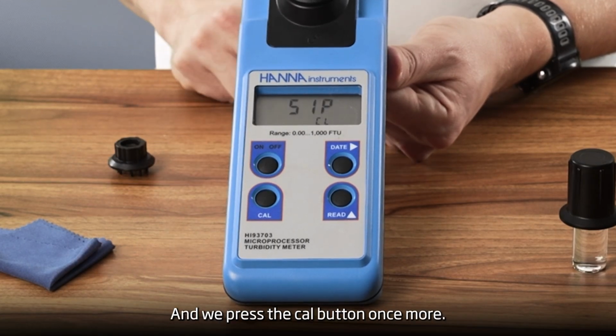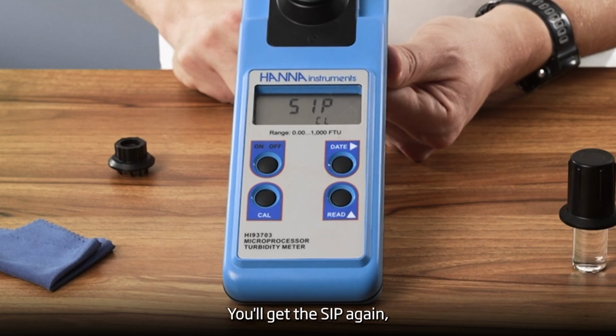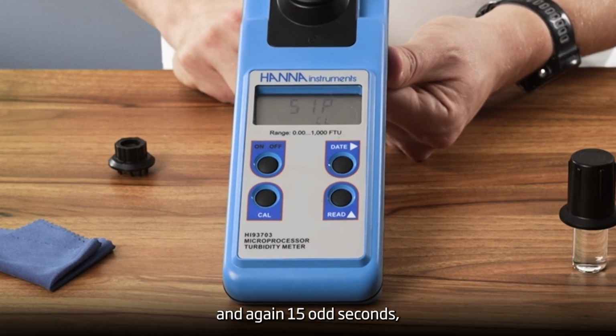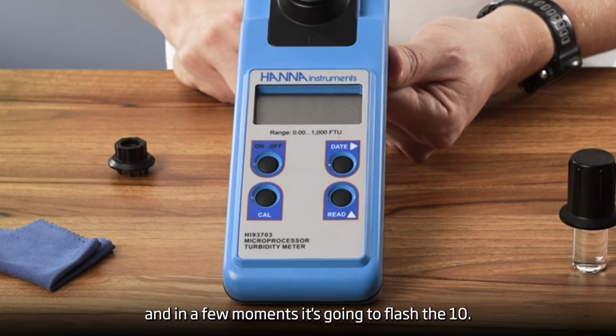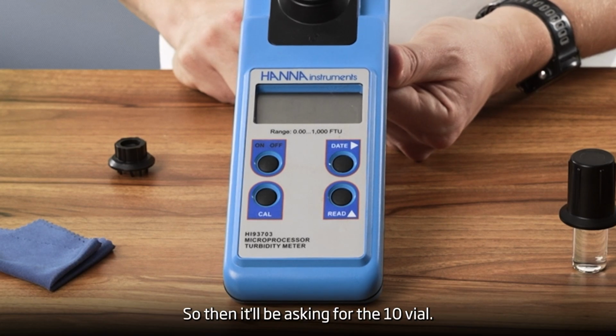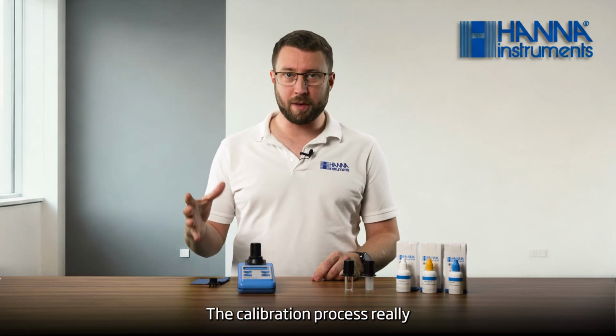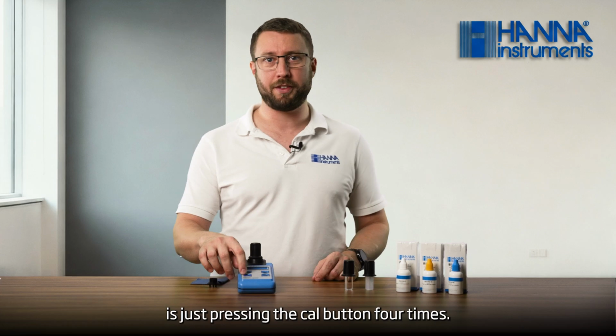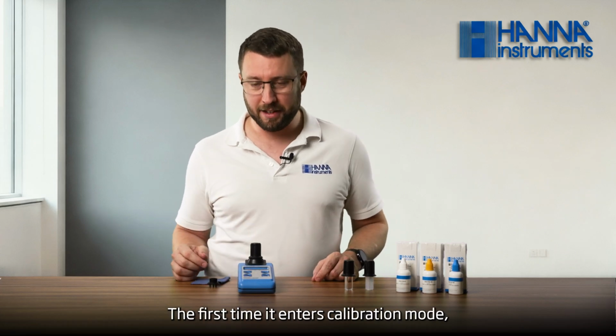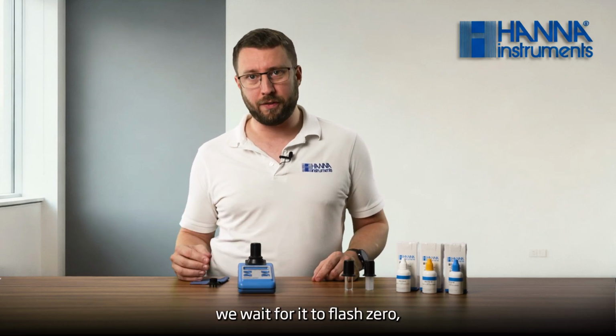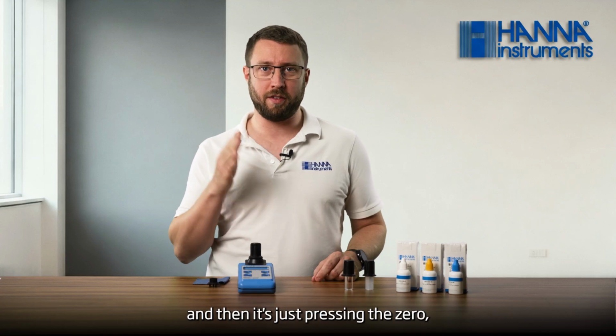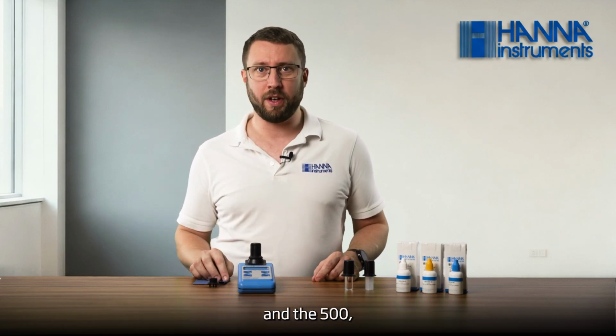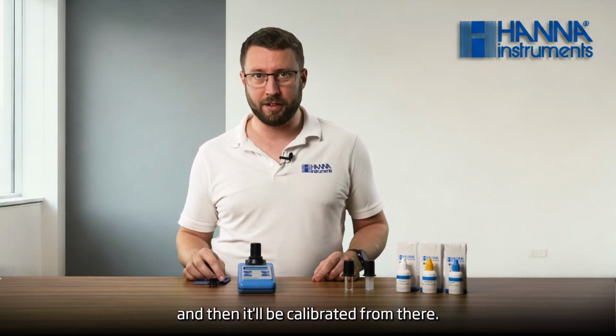And we press the cal button once more, you'll get the SIP again, and again 15 odd seconds, and in a few moments it's going to flash the 10, so then it'll be asking for the 10 vial. The calibration process really is just pressing the cal button 4 times. The first time it enters calibration mode, we wait for it to flash 0, and then it's just pressing the 0, the 10 and the 500, and then it will be calibrated from there.